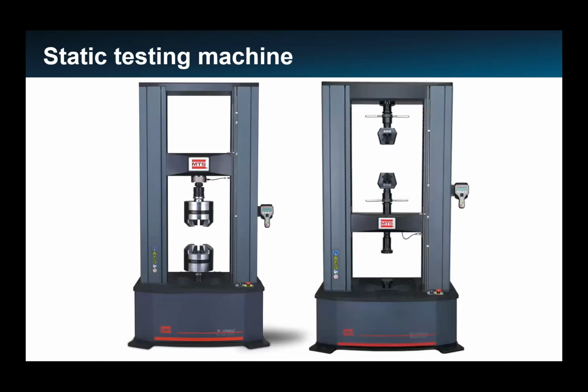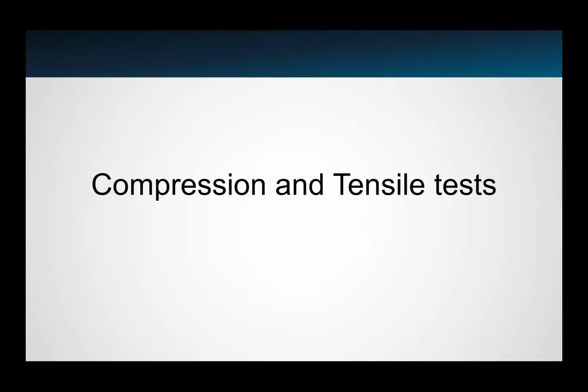This is a machine which is quite different from the one that we showed before. The machine that we showed before can only measure up to 2,000 pounds, and this can actually measure up to 67,000 pounds. I would say that with the first machine we can calculate the results more precisely. The universal testing machine can be used to test various types of materials, including metals, plastics, rubber, ceramics, and composites. The machine can be used to perform several tests, but in this presentation, we will focus on tension and compression tests.